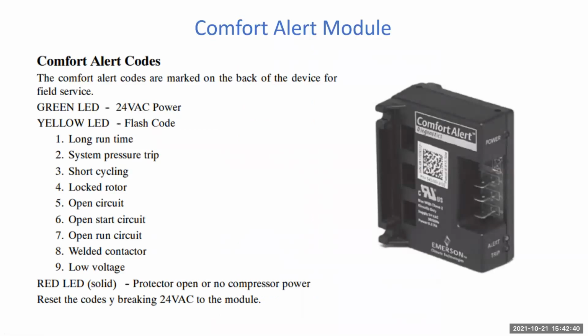We also have comfort alert systems on a lot of our geos. For the comfort alert diagnostic, it's monitoring the device. Sometimes it'll give you a shutdown. It'll shut down the compressor depending on how they're installed and which units. Most of these are on the GT series. When you have an abnormal condition, the comfort alert module will display the alert and the trip LED. The yellow is the alert, and it'll flash a certain number of times. Like any error code, it's giving you the general vicinity. You want to troubleshoot a little bit. Don't just assume that the comfort alert knows exactly what it's doing. So the comfort alert, every time it powers up, will flash the last alert that occurred prior to the shutdown.